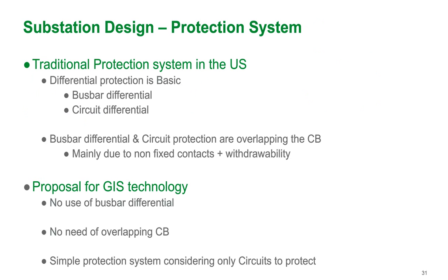Now protection is another area where you can focus on for cost reduction by utilizing gas insulated switchgear. So traditionally in the U.S., we see a lot of bus bar differential protection, a lot of circuit differential, so isolation of the circuit breaker is a failure point. The proposal with GIS is that there's no need for or no use of bus bar differential, and there's no need for overlapping protection of the circuit breaker, simply because those are not common failure sources. So you can simplify your protection and therefore lower the cost just by eliminating those extra relays and extra instruments.